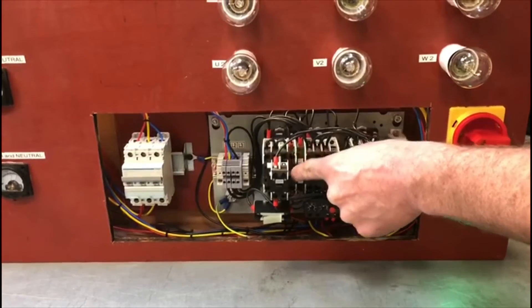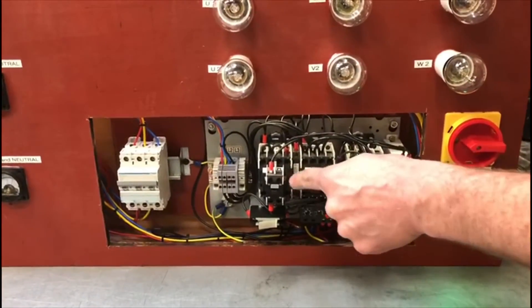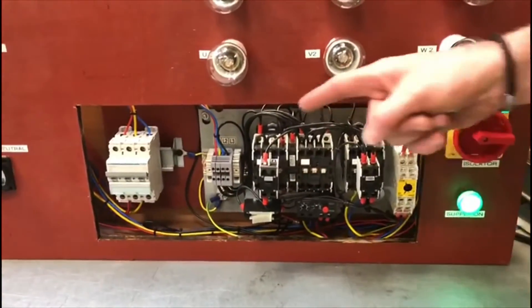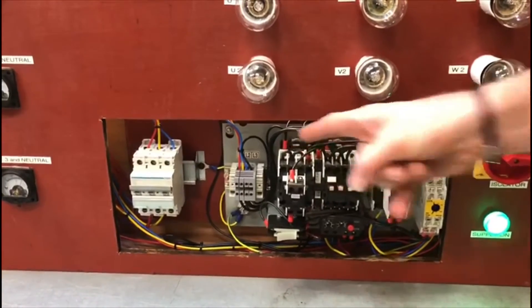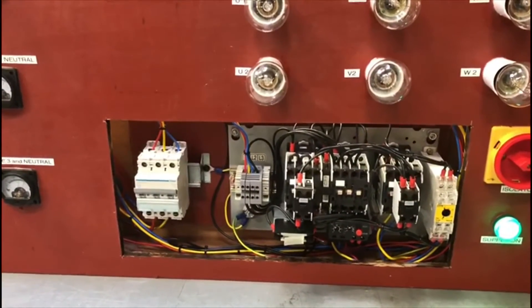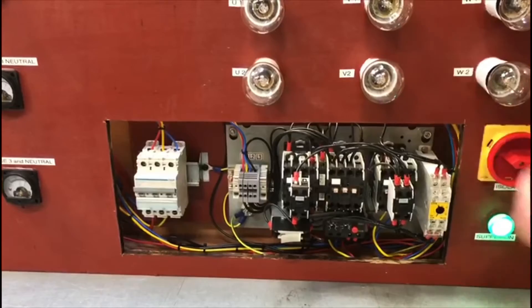As soon as this one pulls in, this one on the left-hand side is also pulled in, and that's the star contactor. You can tell it's the star contactor simply by looking at the top of it. You can see how the top has been linked out.